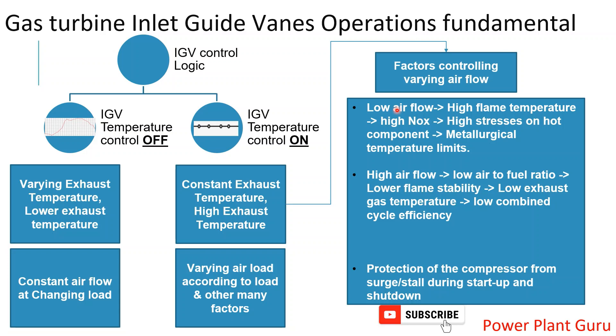This is how, on a broad level, you can understand how IGV operates. There are many other minute factors — such as the temperature control constants and the isothermal temperature limit — which we can discuss in another video. Another point is that the IGV also modulates during startup and shutdown. During startup, if too much air is admitted, it will not allow the flames to stabilize and the flame will be extinguished. That is why IGV is controlled carefully during startup.